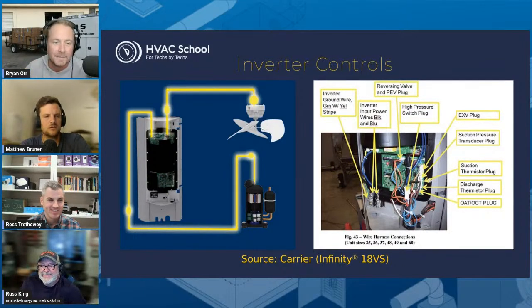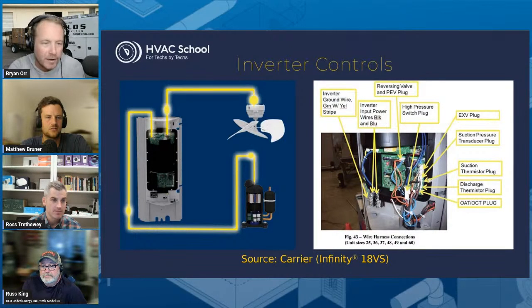The next thing is, go ahead, Matt. Could you speak a little bit to the mass flow rate? Yeah, right. Because that's the thing: as your outdoor temperature decreases, when you're running a heat pump in heat mode, your evaporator is now outdoors. And the colder it gets, the lower your suction saturation drops, the lower your suction pressure drops. That's how that works. And so your suction saturation and suction pressure are always going to be lower than your outdoor temperature. So if it's -5 degrees outside, you're going to have an evaporator coil that's lower than that.